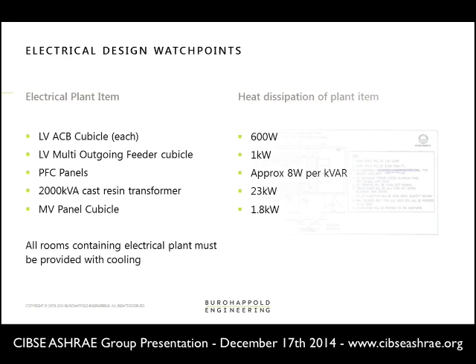The other thing that often catches people out is cooling for all electrical plant. Here's a typical heat dissipation for plant items. Each LV-ACB cubicle is 600 watts of heating load, or a multi-outgoing feeder cubicle is a kilowatt. Power factor correction, about 8 watts per kVAR. A 2 MVA cast resin transformer is about 23 kilowatts. And an MV panel cubicle is about 1.8 kilowatts. And that's in addition to the loads provided by the outdoor conditions.